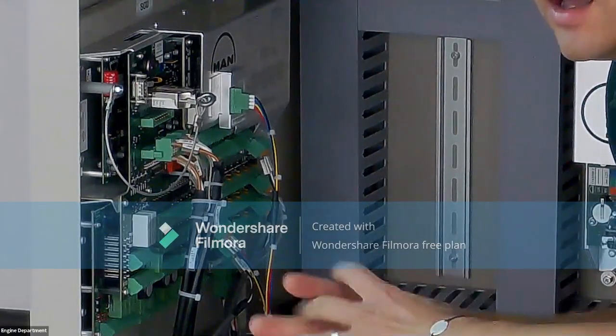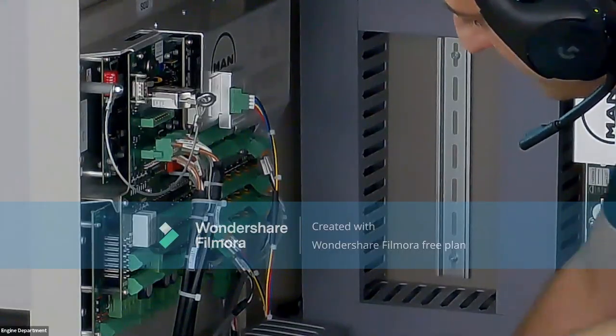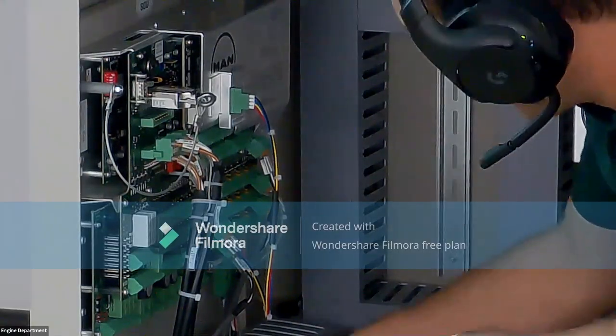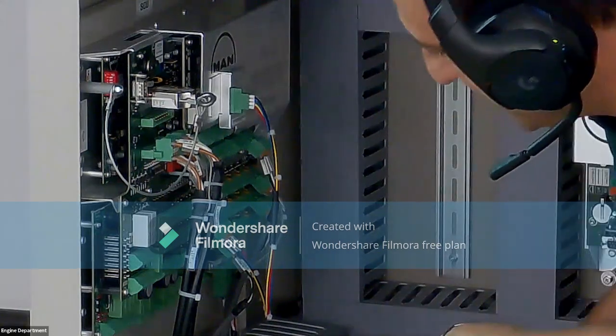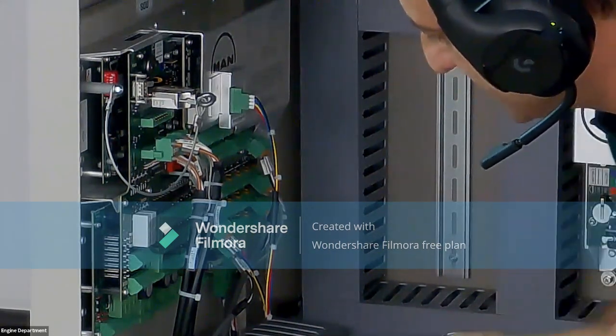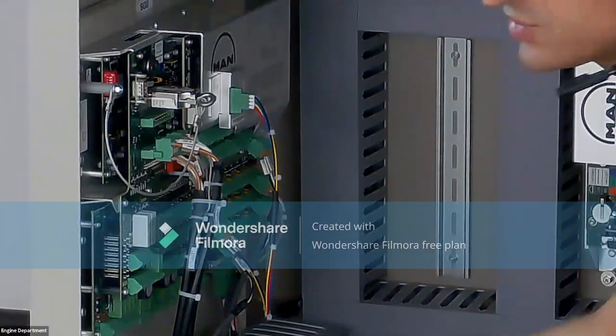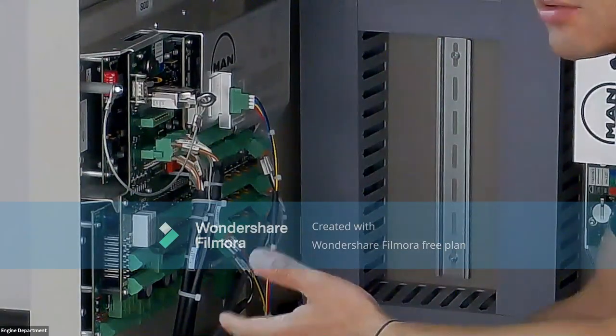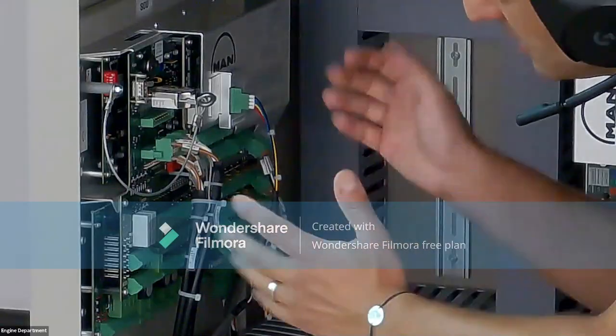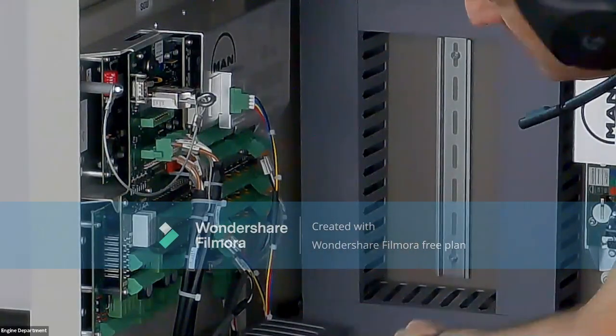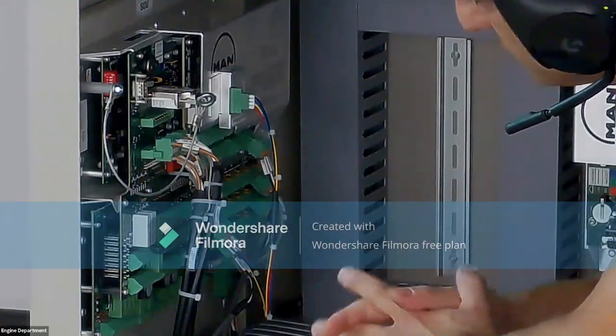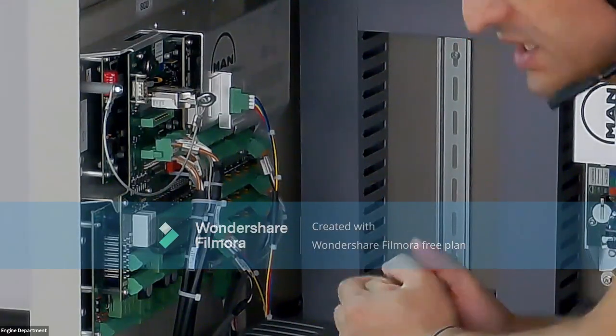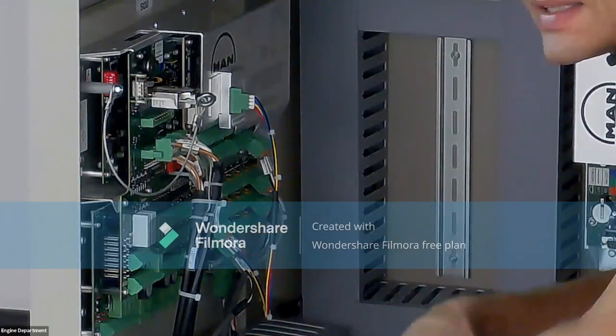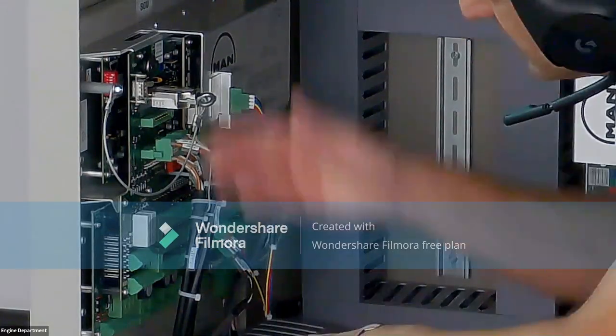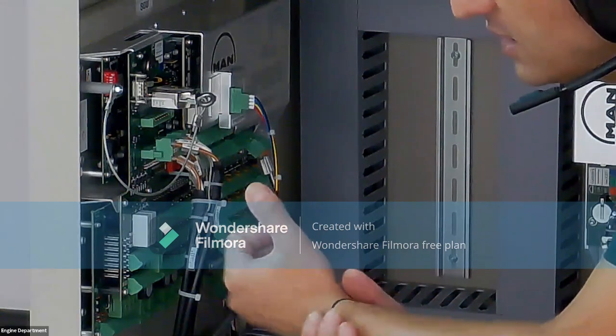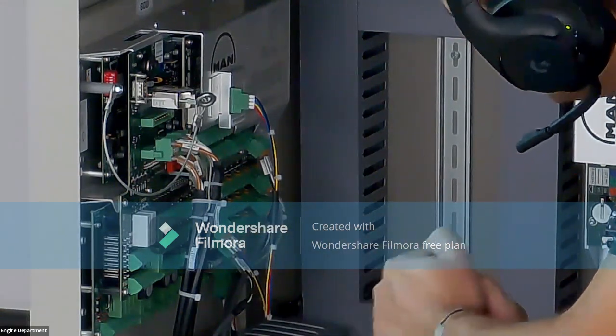Before starting any replacement of the MPC, or now that we are aware that the MPC is damaged, in case you are just replacing it or testing it, you are interchanging the MPC. Before starting, please touch the cabinet several times in order to discharge yourself, so as not to create electrostatic discharge between you and the electrical components of the MPC. Nowadays, MAN also offers a strap which is connected to your hand and to the cabinet in such a way as to always have the same electrostatic charge.